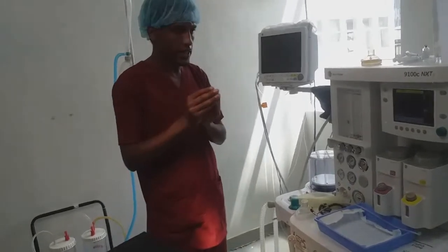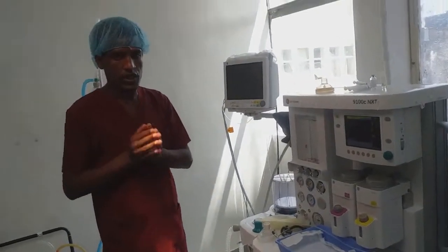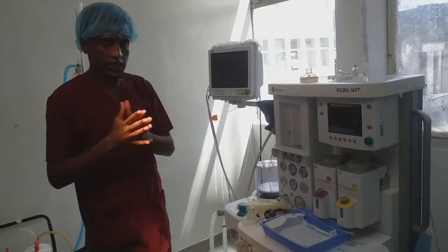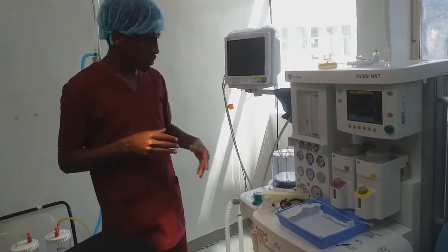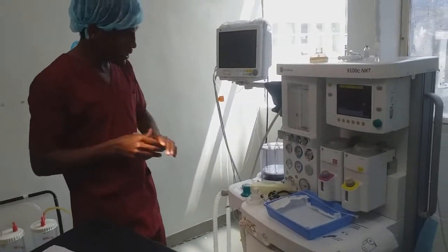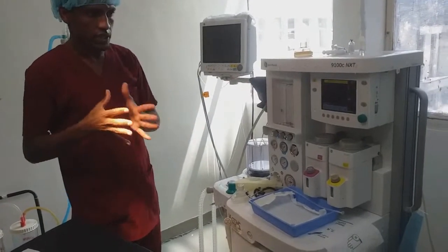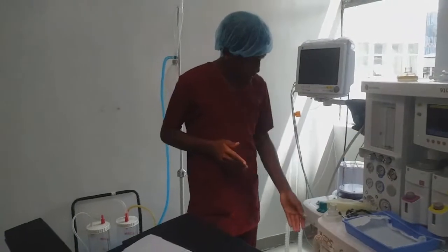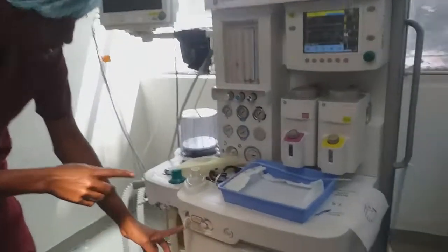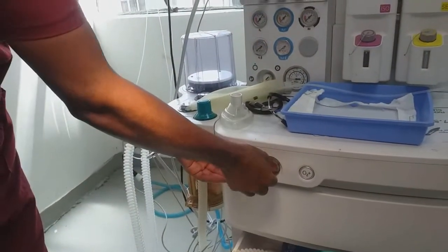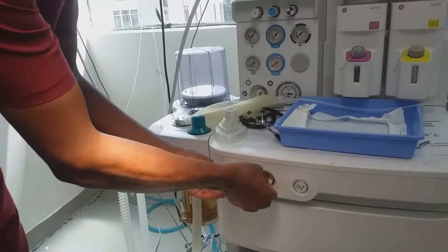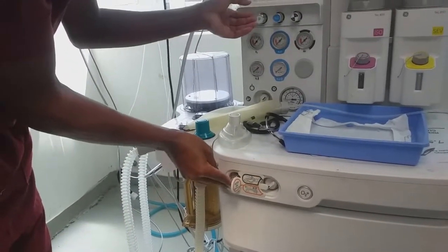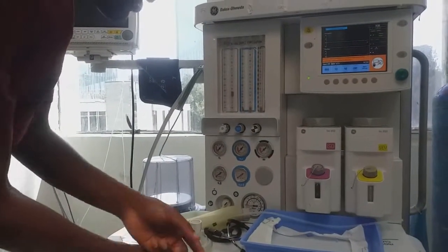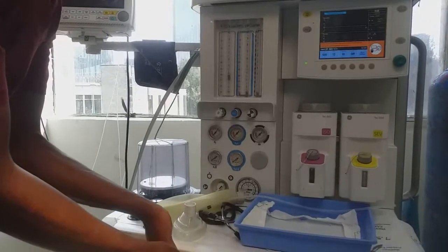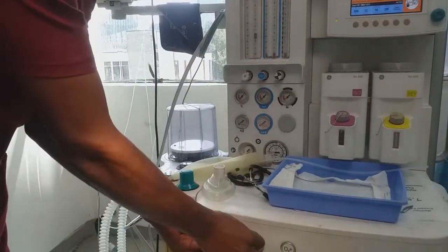Sometimes we also use the auxiliary oxygen flow method for support or for oxygen supplement for the patient, as well as during jet ventilation. We also use the oxygen flow method, nasal flow method, or auxiliary oxygen flow method. Some machines have their own auxiliary flow methods, but in this machine we use the common gas outlet as the auxiliary oxygen flow method. Now I'm converting to this common gas outlet. This indicates the auxiliary oxygen flow method. We use this as the auxiliary flow method.